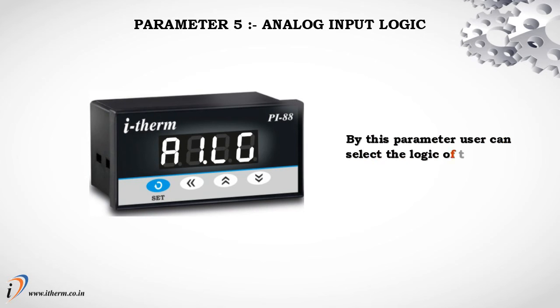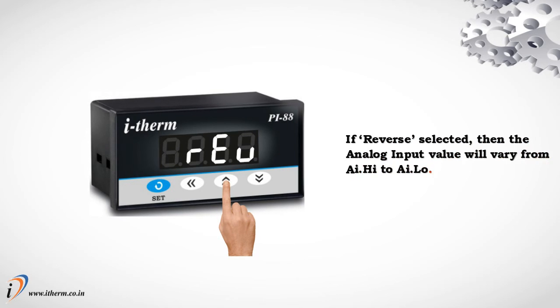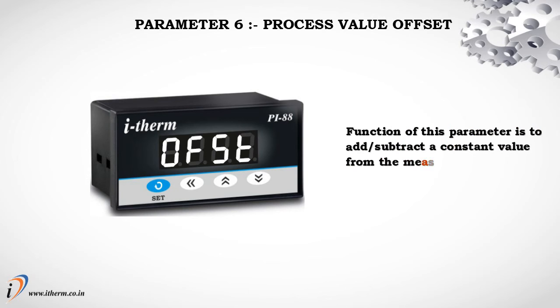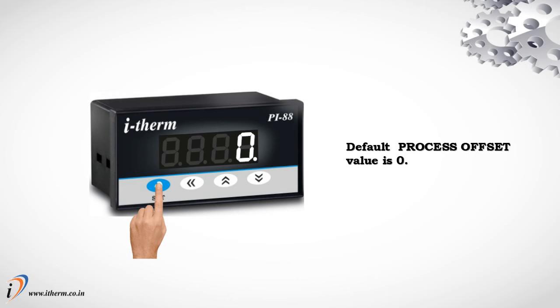Parameter 5: Analog Input Logic. By this parameter, the user can select the logic of the analog input. If direct is selected, the analog input value will vary from analog input low to analog input high. Parameter 6: Process Value Offset. The function of this parameter is to add or subtract a constant value from the measured process value to obtain the final process value for control applications. The default process offset value is 0.